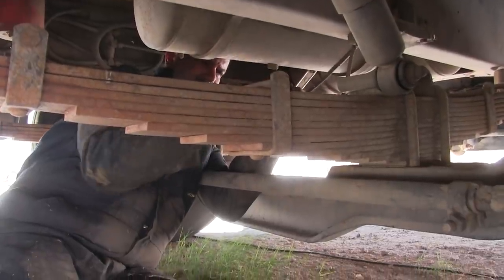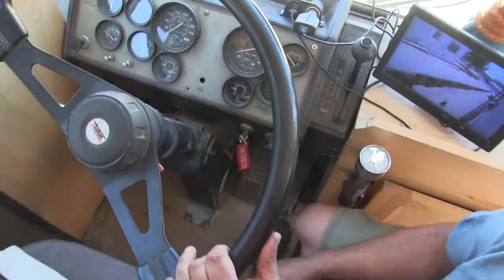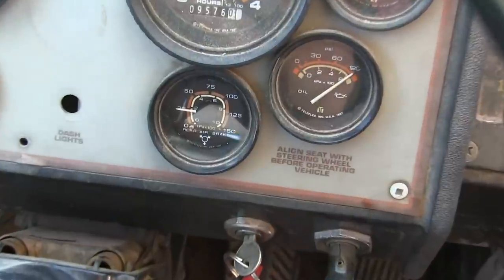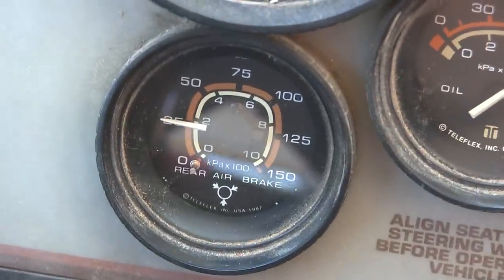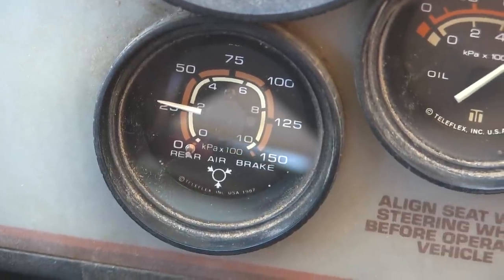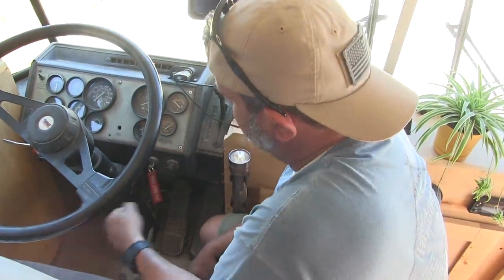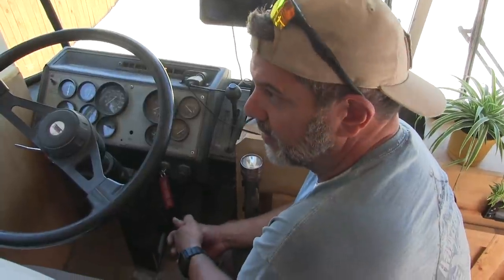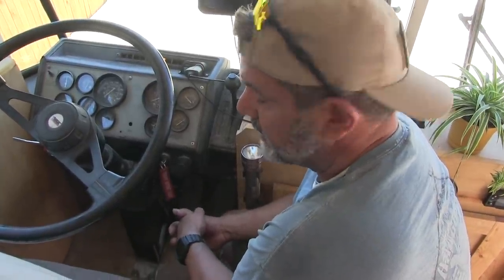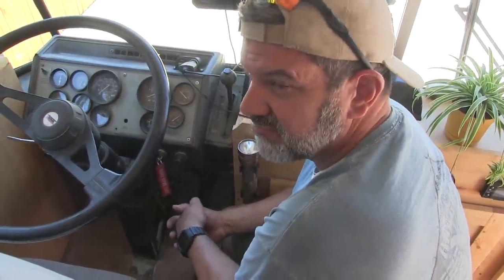I think in the box is some Teflon tape over there, is there? So pressure's actually going up faster than it used to, which would suggest our compressor wasn't working as efficiently as it could. As soon as it gets up to 60, it'll stop making ding-dong noises. And then we need to get it up to the unloading pressures and make sure everything unloads. And if it does, we win. Hooray!